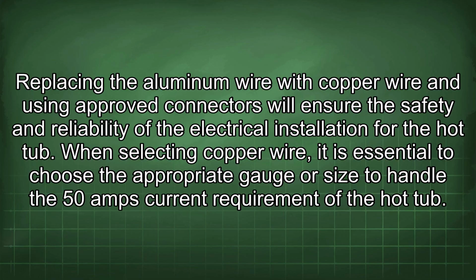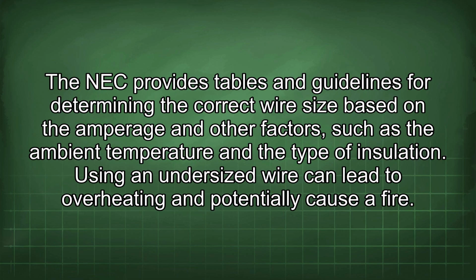When selecting copper wire, it is essential to choose the appropriate gauge or size to handle the 50 amps current requirement of the hot tub. The NEC provides tables and guidelines for determining the correct wire size based on the amperage and other factors, such as the ambient temperature and the type of insulation. Using an undersized wire can lead to overheating and potentially cause a fire.